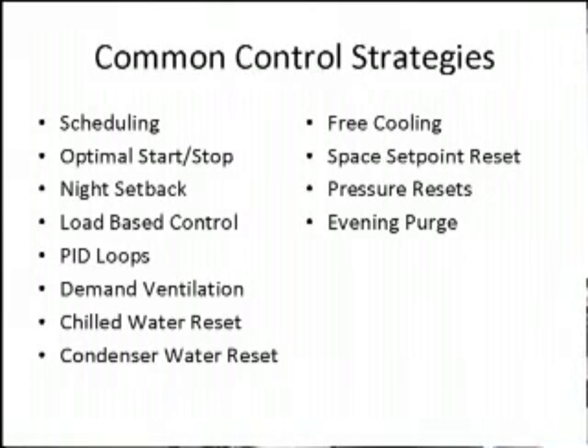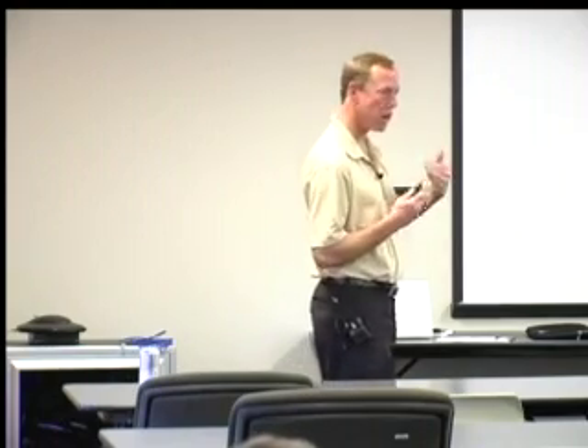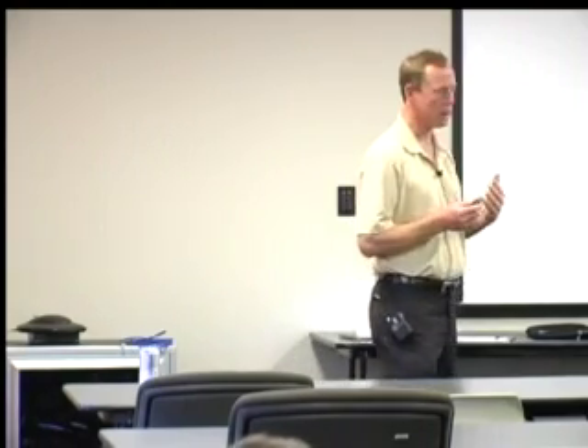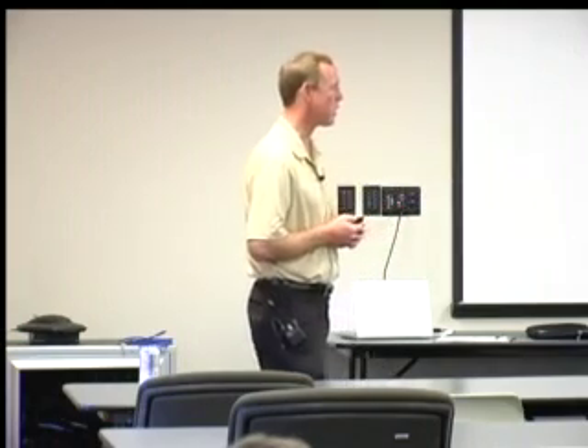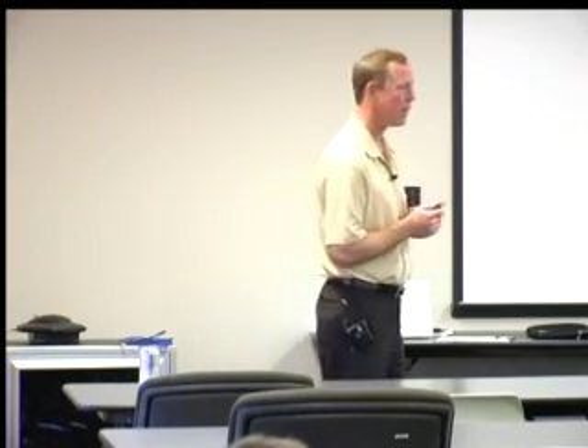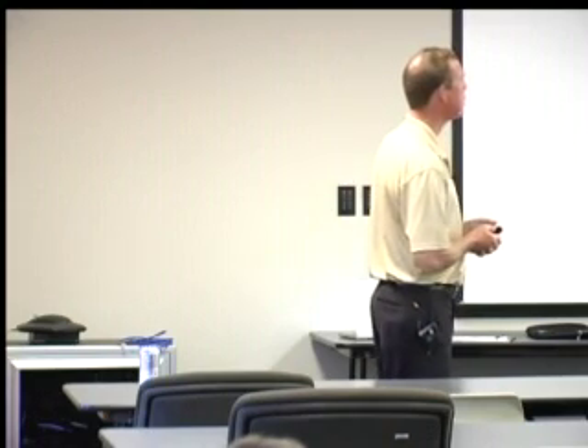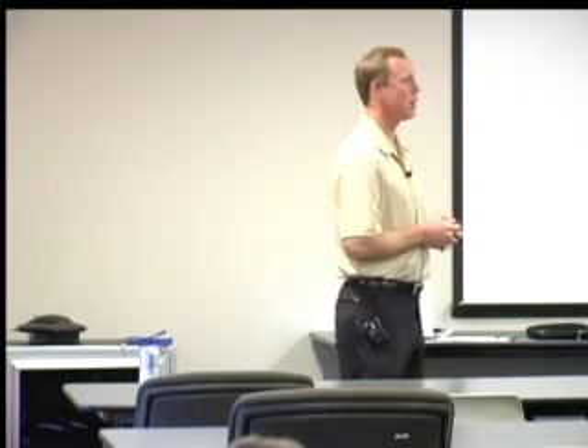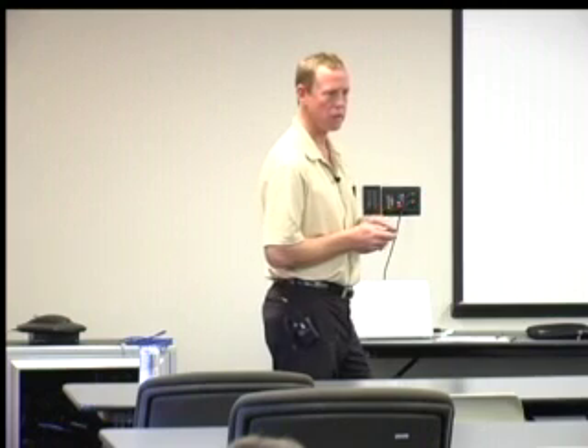Optimal start and stop goes along with scheduling. If you do a setback or shutdown at night, it's a means to get your building back conditioned perfectly for the people — when the first person walks in the door, you want it in perfect condition without using any more energy than you had to. So it tries to predict the perfect time to start up the systems, depending on inputs like outside air temperature, outside humidity, indoor conditions, and how fast your equipment can recover.